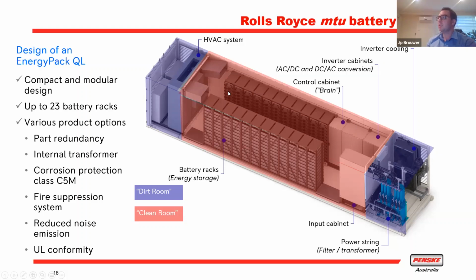This whole system is cooled on two fronts. One front is inverter cooling, where most of the heat is generated, and this cooling system is water-based, so it's very efficient as a result. As a safety precaution, we also have an additional HVAC system, especially required when operating in high temperature environments, to make sure the temperature of the batteries as well as the other electronics remains at a cool level.